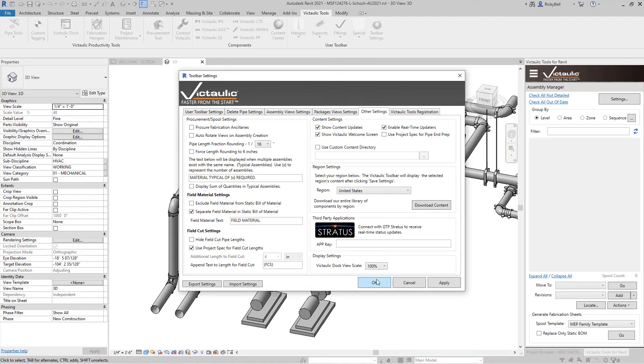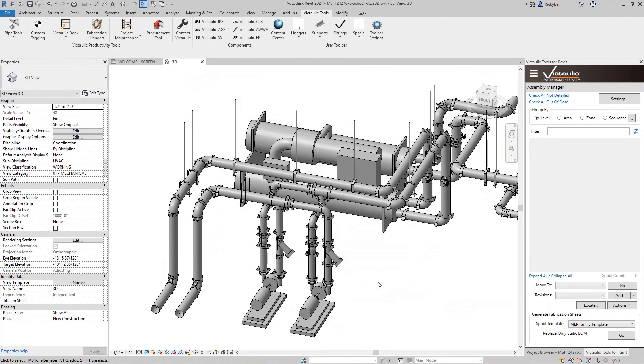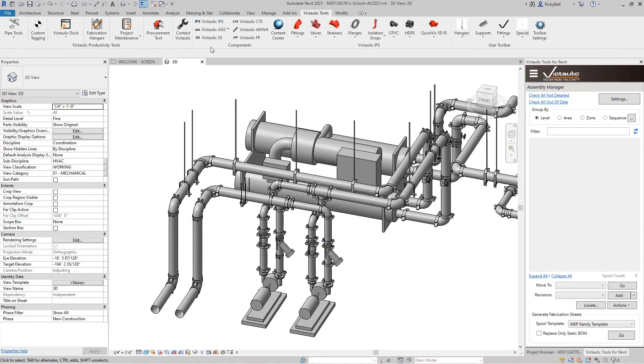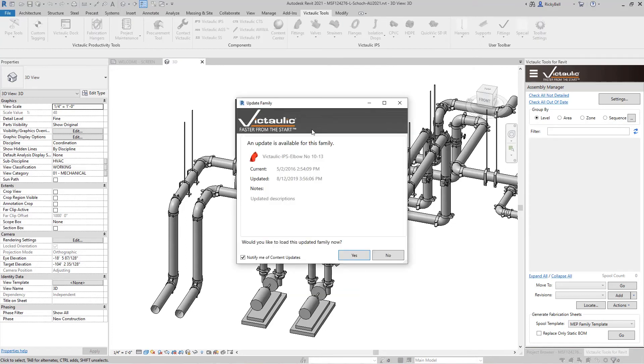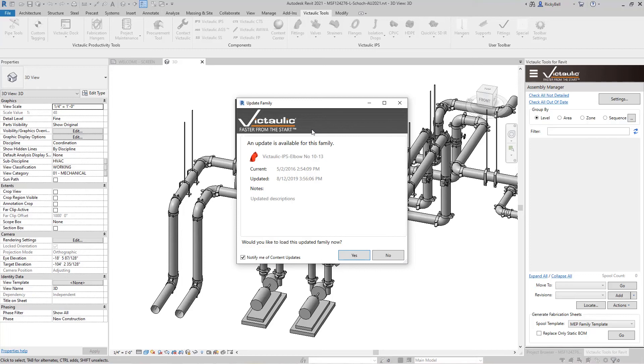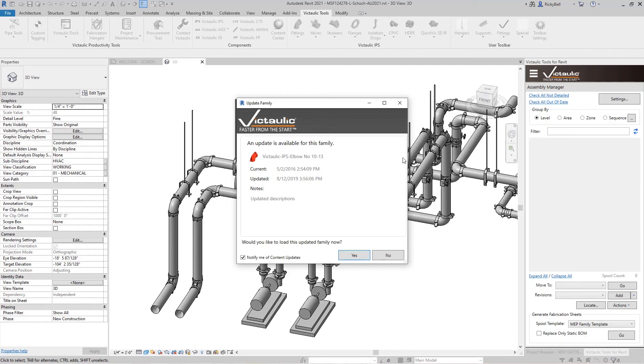And whenever this is checked if there's a newer version of whatever family you're asking Victaulic Tools for. I'll use the elbow family for example. If there's a new version available you will get prompted with a yes or no question. Would you like to update this family now? And this becomes important if any of these updates were to change end to end lengths or any other dimensions that would affect your pipe lengths. It's important to us that you're able to get accurate pipe lengths in your bills of material. So this is just the first way to make sure your content is up to date.